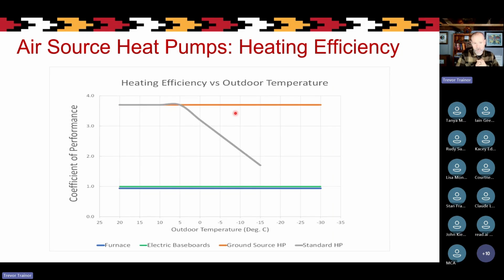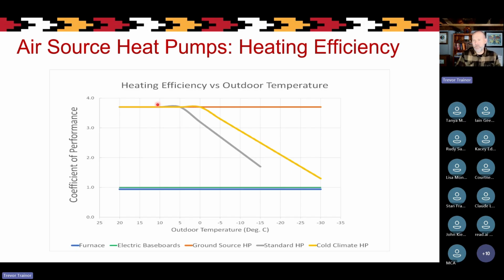When we start to look at air source heat pumps, though, there's some limitations. That standard air source heat pump starts to drop off in its performance quite quickly once we get below about 10 degrees, to the point where by the time we're at -15, it's at about 1 to 1.5 coefficient of performance. So it's not nearly as efficient at -15 as it was at 5 or 10 degrees. The cold climate heat pump, though, performs a lot better and drops off a lot more slowly. So even at -15, it still has a coefficient of performance of about 2.5. So it's still 2.5 times more efficient than electric baseboards at -15.